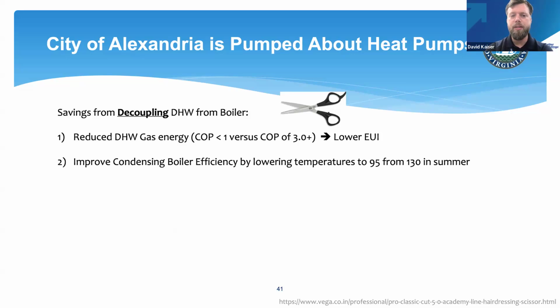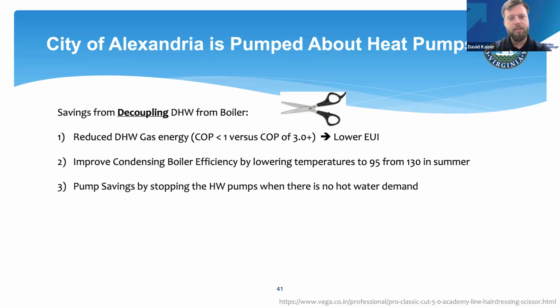We improve the condensing boiler efficiency. Some people don't recognize this, but just because you have a condensing boiler doesn't mean that you have a high efficiency system. It depends on the operating temperatures that you use. So if you go downwards towards 110 degrees or lower, that means you have a more efficient boiler itself. So that provides some savings. Next, please. Pump savings are there by stopping the hot water pumps during the summer.